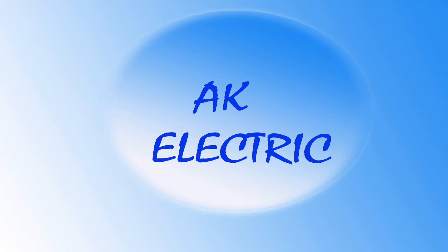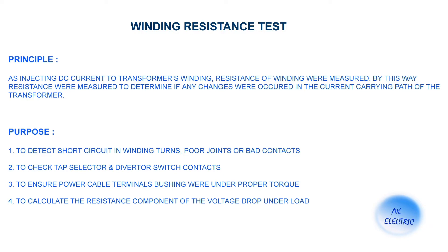Hi friends, welcome to AK Electric YouTube channel. Now we are going to see winding resistance test. Principle: by injecting DC current to transformer windings, resistance of windings is measured. By this way, resistance is measured to determine if any changes have occurred in the current carrying path of the transformer.